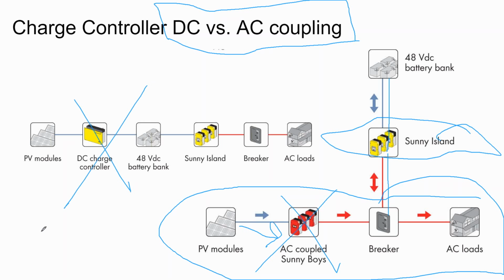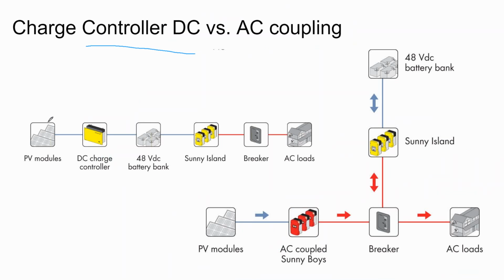That said, when I'm designing systems completely from scratch, I prefer DC coupling because it provides that extra level of security. Also, unlike a grid connected home where the battery just sits there until a power outage, on an off grid home your batteries are used for the vast majority of the day. Your solar array may only be on for 8 to 10 hours, a third of the day, so you're relying on your batteries much more. That's where the two-step process comes back into play: DC coupled systems are slightly more efficient than AC coupled systems.